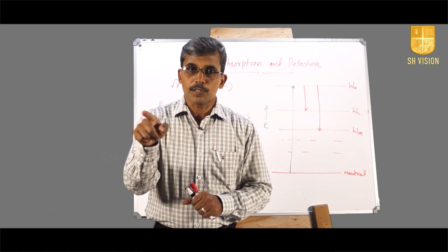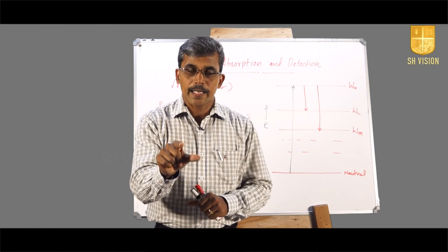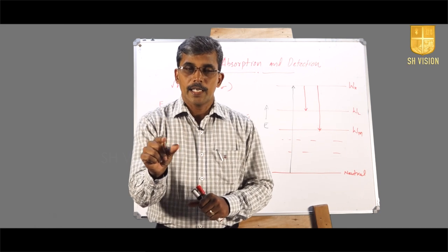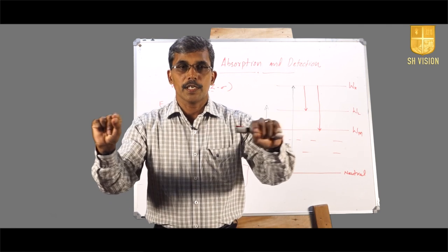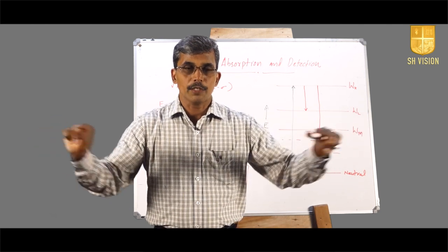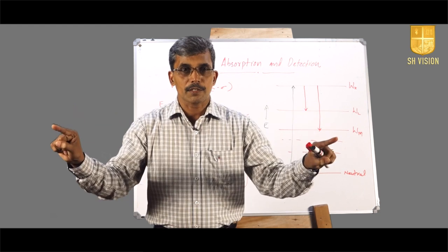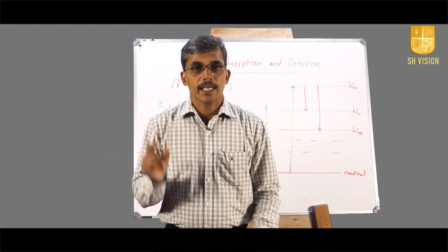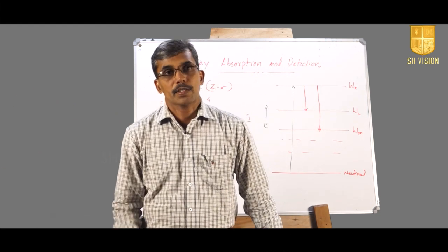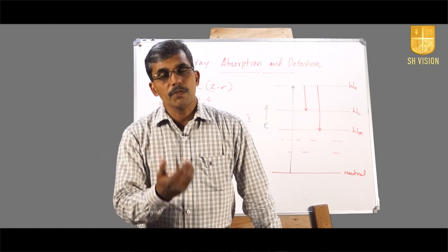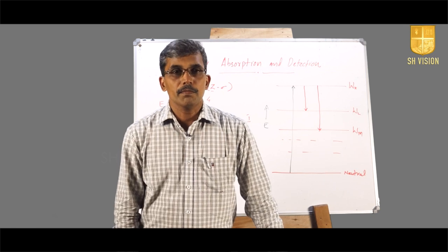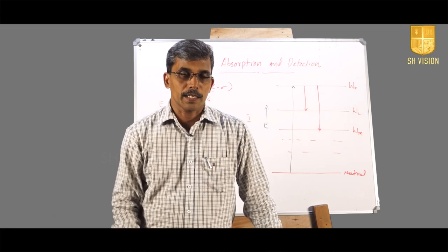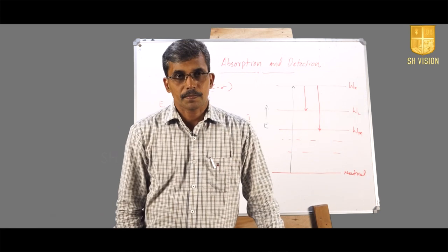When X-ray passes through this gas, atoms will be ionized, and you will get positive ions and negative electrons. These are attracted towards the electrodes, and when they come in contact with the electrode, immediately a surge current will be indicated at the output. That is the information. That is how we are able to detect X-ray coming from the material from where it got diffracted.